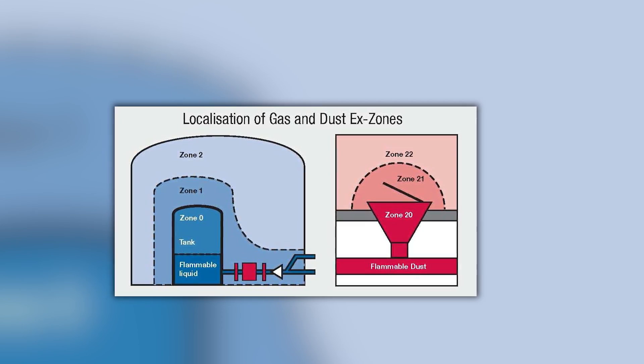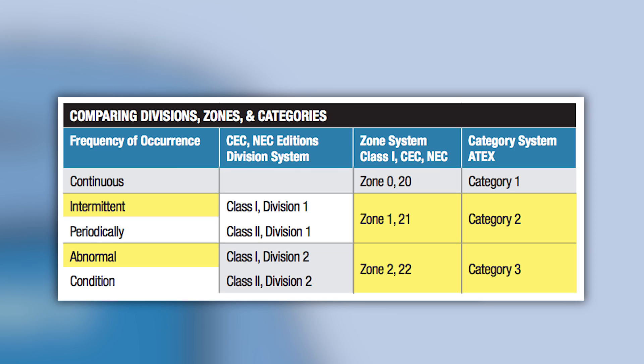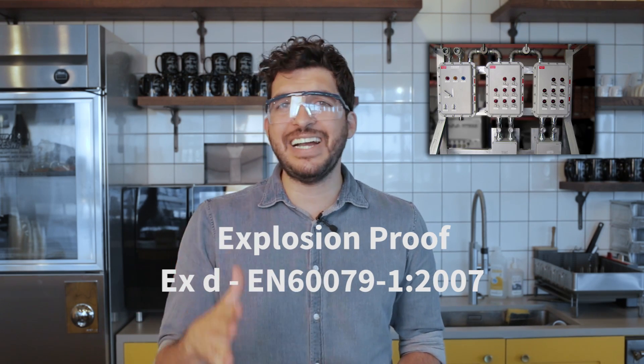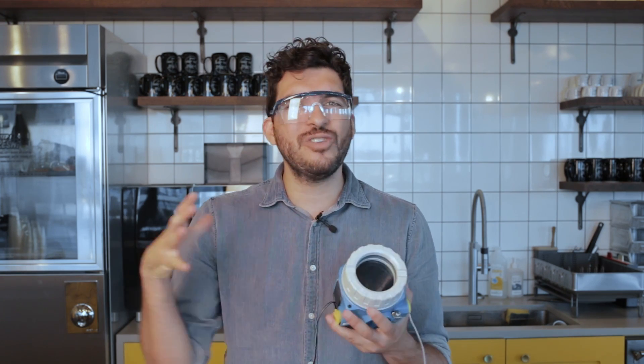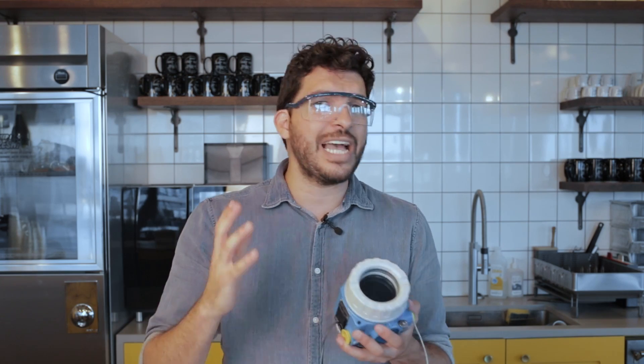Additionally, ATEX describes the zones in which explosive atmospheres are present and the probability of this happening. In the oil and gas and chemical industries, explosion-proof devices, or Ex d devices, are used. These devices, like this transmitter here, are able to contain the explosion inside their volume. For example, this transmitter has a thicker glass that will not allow the explosion gases to reach the surrounding atmosphere.